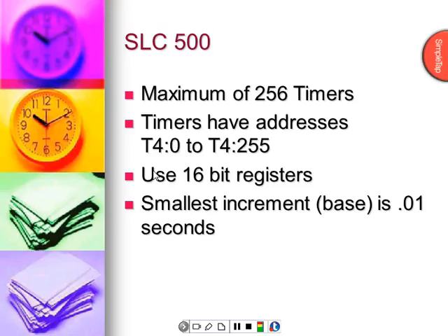Alright. The SLC 500 series, which is the PLC we've been using, has a maximum of 256 timers. They are addressed, please remember this, T4:0 to T4:255.